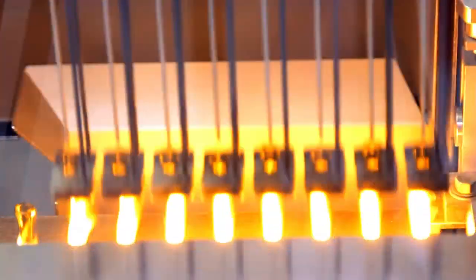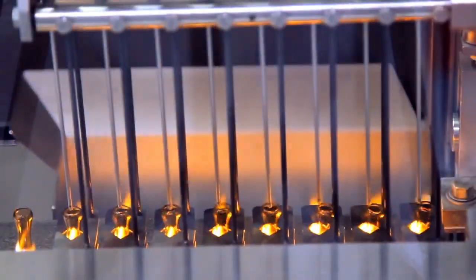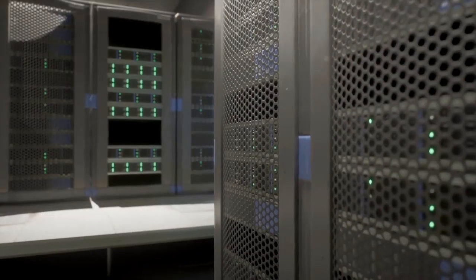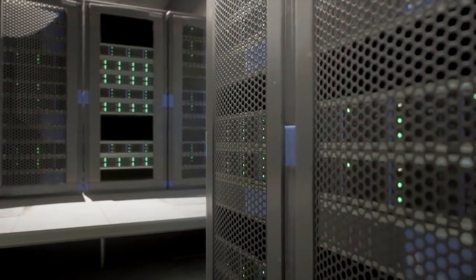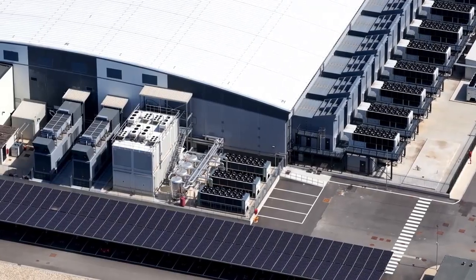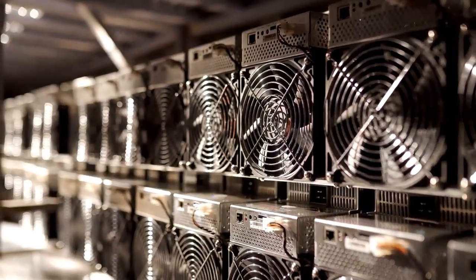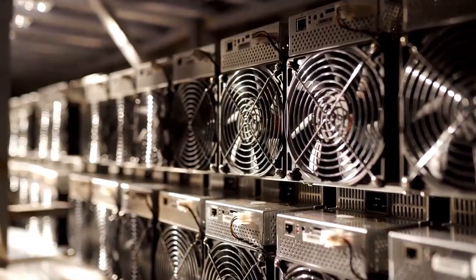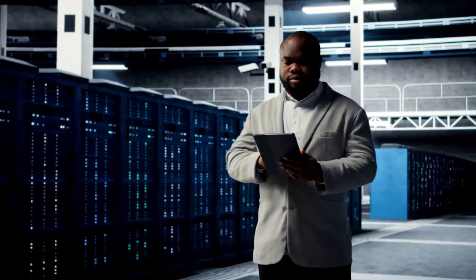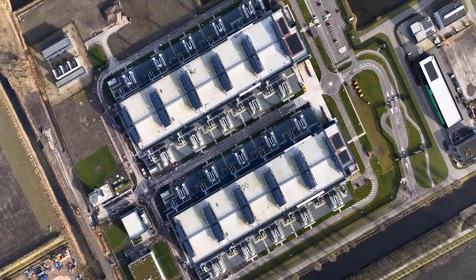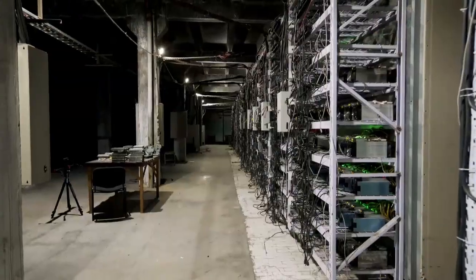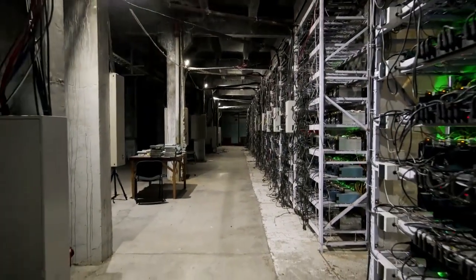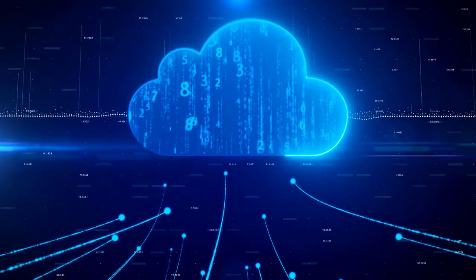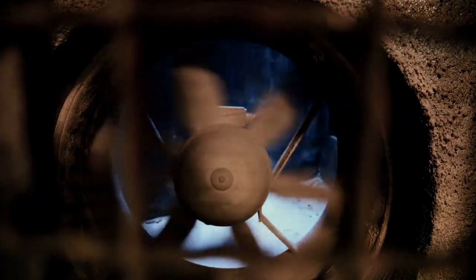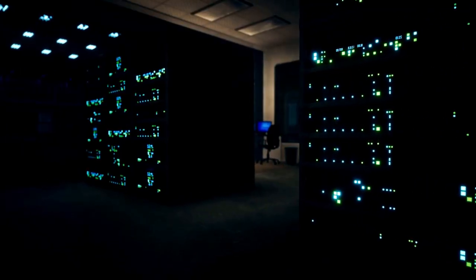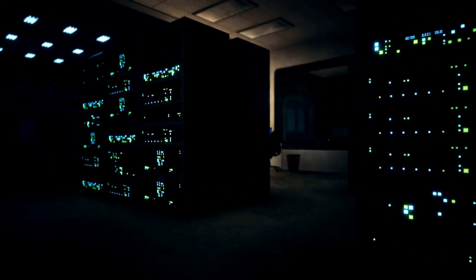Transferring heat from a solid object into passing air is a slow, highly inefficient process. When data center rack power densities were low, hovering around the 5 to 10 kilowatts per rack range, the glaring inefficiency of air was perfectly manageable. Facility operators simply scaled up the brute force. They built larger computer room air handlers, implemented strict hot aisle and cold aisle containment systems to prevent the mixing of exhaust air, and spun the server fans at higher revolutions per minute to push massive, continuous volumes of chilled air through the electronic equipment.